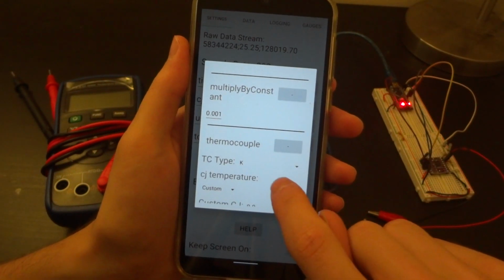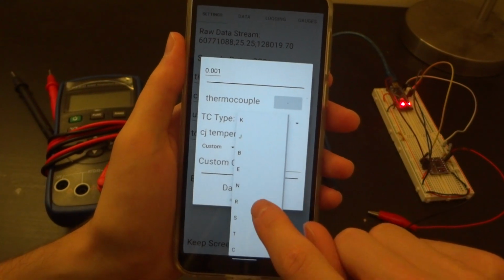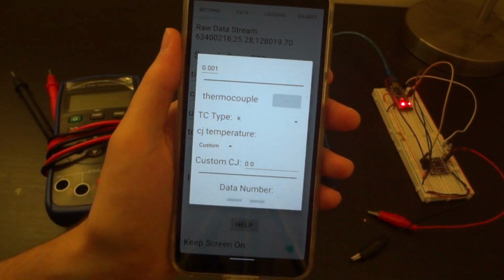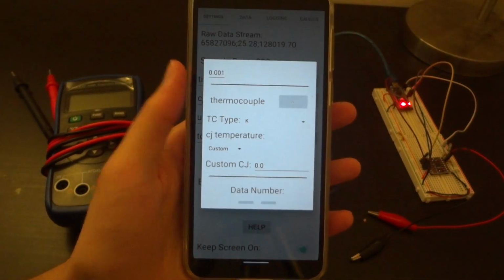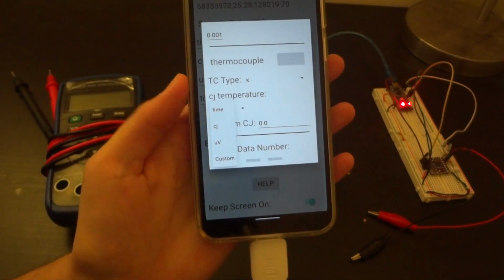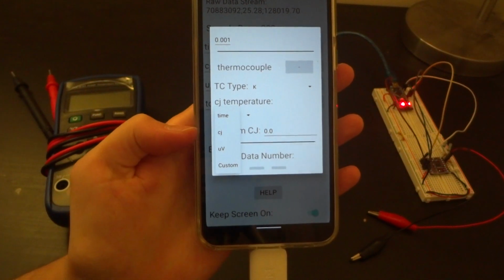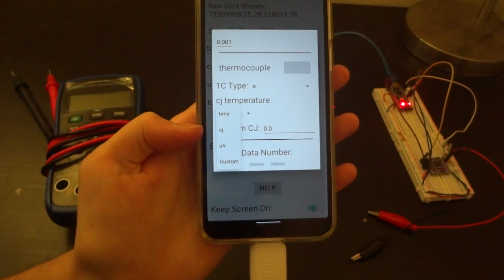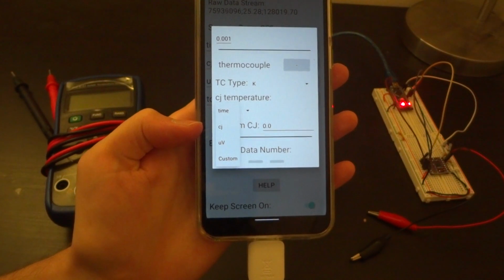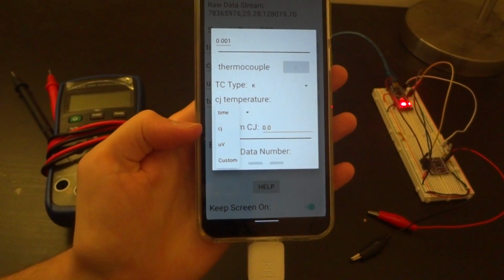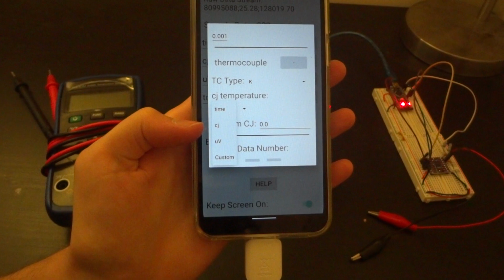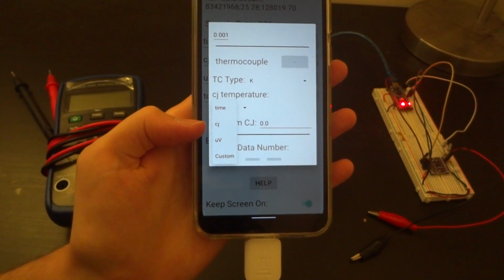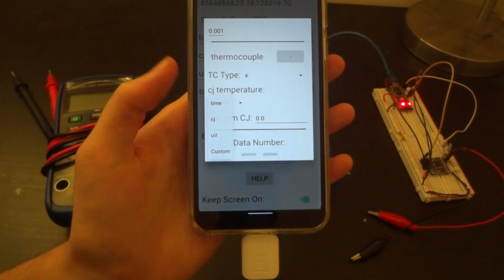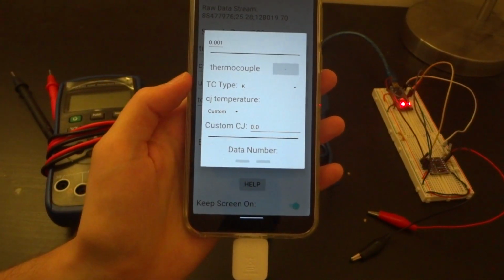Now we can add the thermocouple calculation. You can see here we can change the thermocouple type; we're going to keep it at K type. You can also choose where the cold junction temperature comes from. If we were using the internal temperature sensor of the chip, we could use the CJ data label, but we're going to stick to custom. We could set this to whatever we want, but I'm going to keep it at 0.